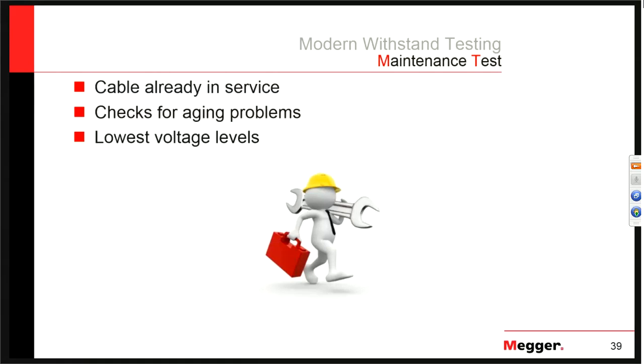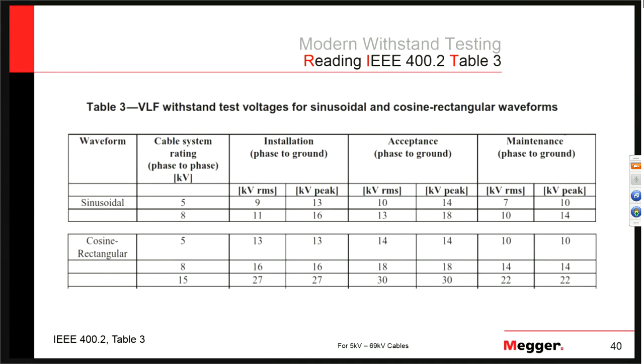Looking at a segment of IEEE 400.2 Table 3, it's very easy to read. Select the waveform you'll be using — dictated by your equipment — then select the voltage rating of your system. For example, a sinusoidal 5 kV cable: decide if you're doing the installation test, acceptance test (splices and terminations done but not yet in service), or maintenance test (cable already in service for a number of years). Maintenance test values are generally about 70–80% of acceptance test values. IEEE has this chart for everything from 5 kV to 69 kV.